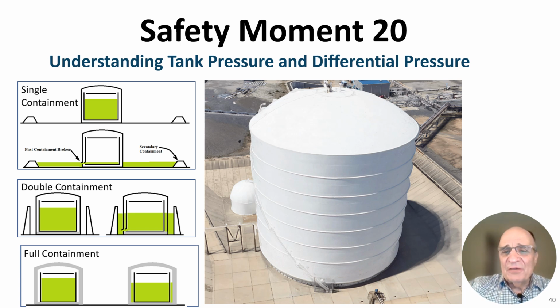The barometer typically changes only within a pound to a pound and a half maximum variation. But when you measure pressures in very low pressure vessels, like an LNG tank that might operate at about 1 psi differential pressure, as your barometer changes, so does that differential pressure, quite significantly. So if I'm reading a tank pressure, I'm really reading the difference between the absolute pressure inside the tank and the absolute pressure outside the tank. A lot of people don't understand that, including many LNG operators, because they're used to just reading the tank pressure, and they say we have 1 psi in the tank today. The BOG pressure in the tank is 1 psi, and when I say BOG, that means boil off gas. And let me talk about that.